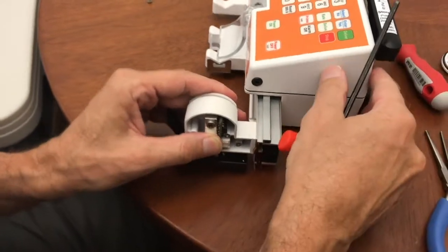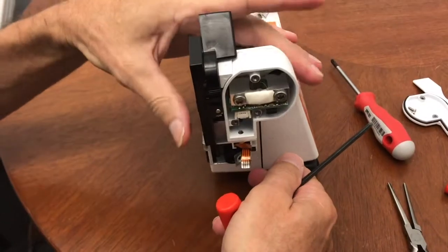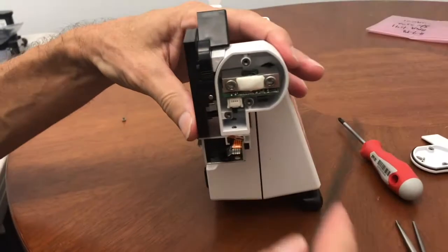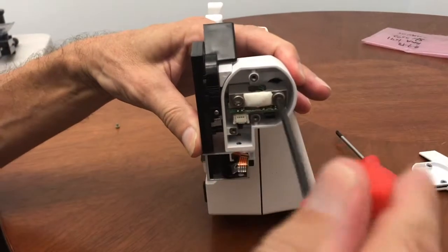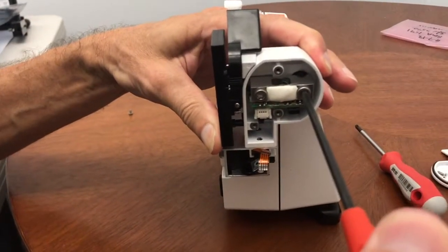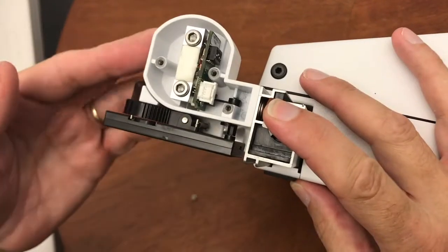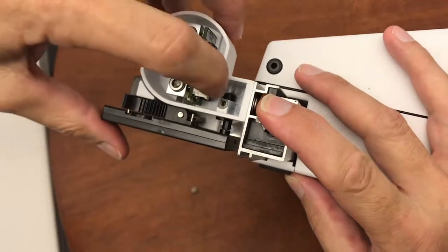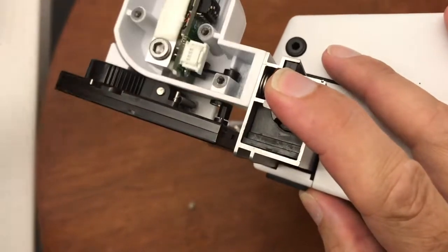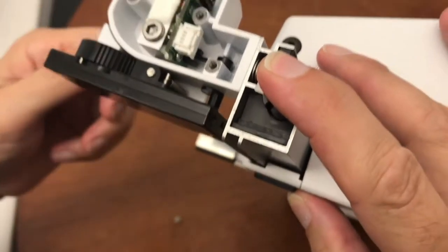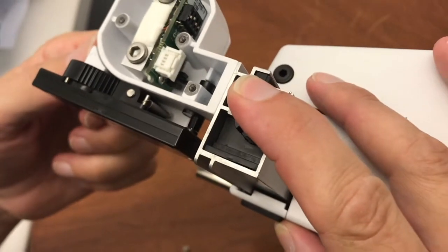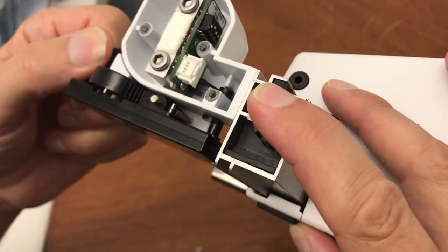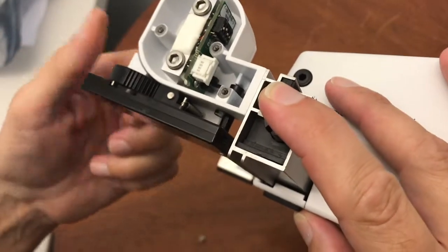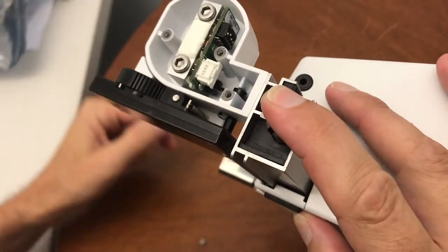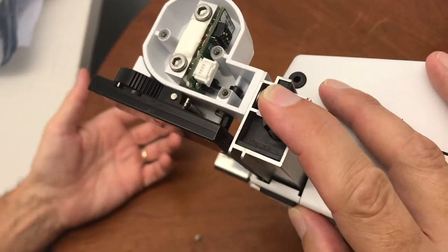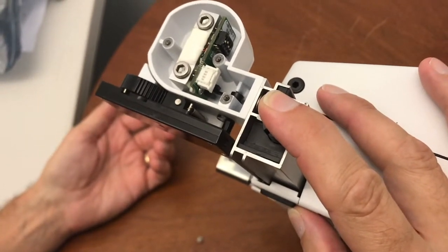Snug up that screw, then it's best as you tighten the screw, push up on this portion of the retainer assembly and then tighten the screw. Note, once that retainer assembly is back in position, that black arm should be in the center of that optical sensor. If you just move the lever slightly, that arm swings out of the way, and then when the lever is released, that arm should go back into that sensor. That's how we detect if there's a syringe loaded or not loaded.